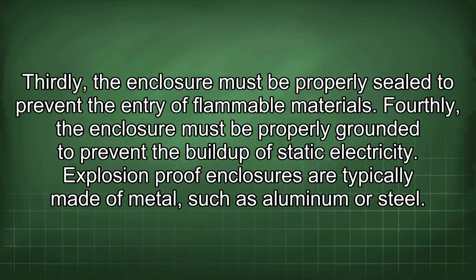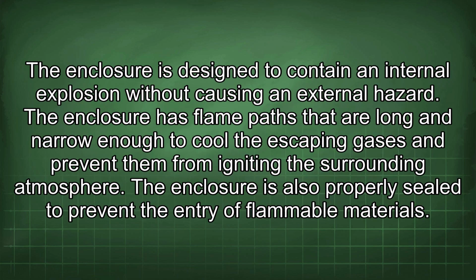Thirdly, the enclosure must be properly sealed to prevent the entry of flammable materials. Fourthly, the enclosure must be properly grounded to prevent the buildup of static electricity. Explosion-proof enclosures are typically made of metal, such as aluminum or steel. The enclosure is designed to contain an internal explosion without causing an external hazard. The enclosure has flame paths that are long and narrow enough to cool the escaping gases and prevent them from igniting the surrounding atmosphere. The enclosure is also properly sealed to prevent the entry of flammable materials.